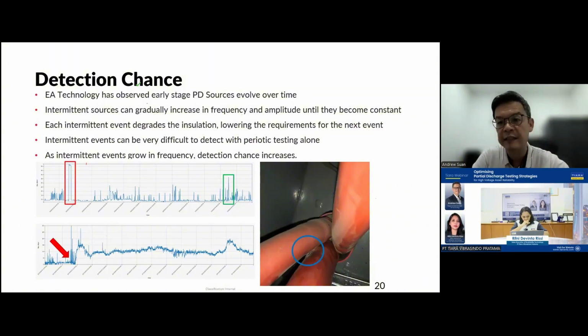Why do these intermittent things happen? It can be because of carbon deposit. When you have a gap in the insulation, there may be arcing, and this arcing may cause carbon to form. When the carbon powder forms, it actually covers the hole, so the PD signal disappears. But inside, the deterioration continues. As the hole becomes bigger, the carbon deposit is not enough to cover it.